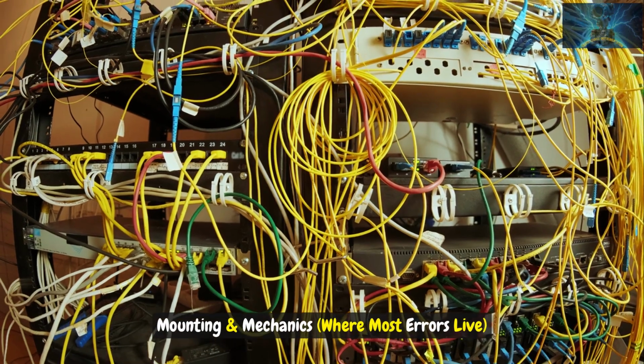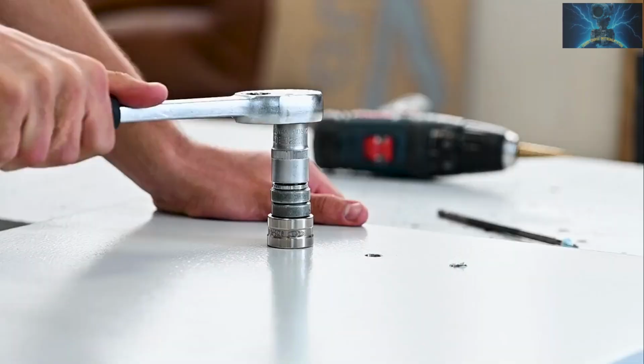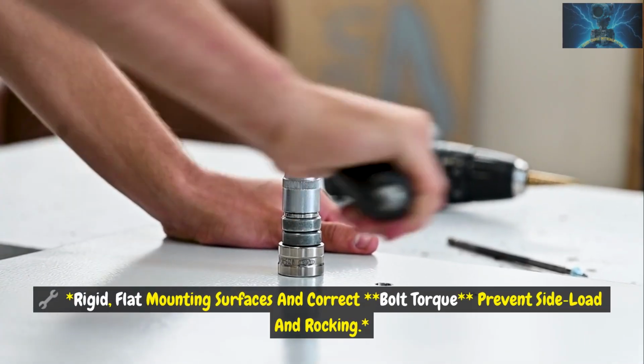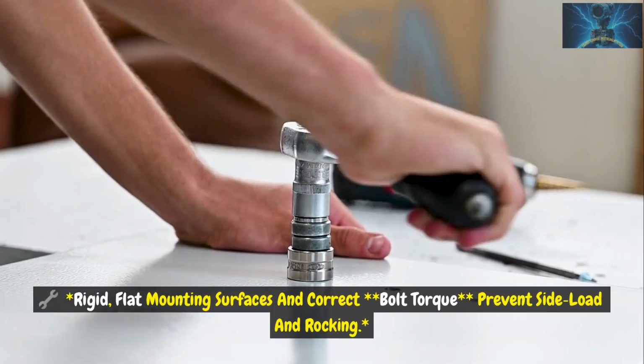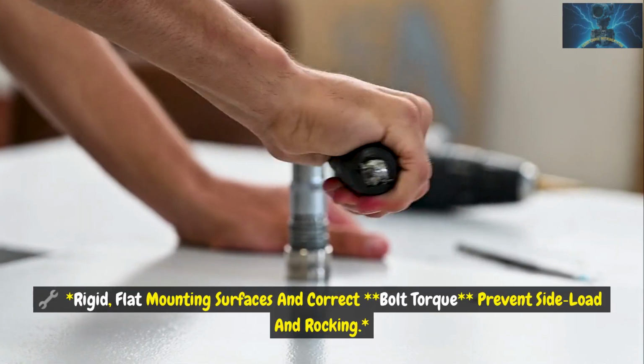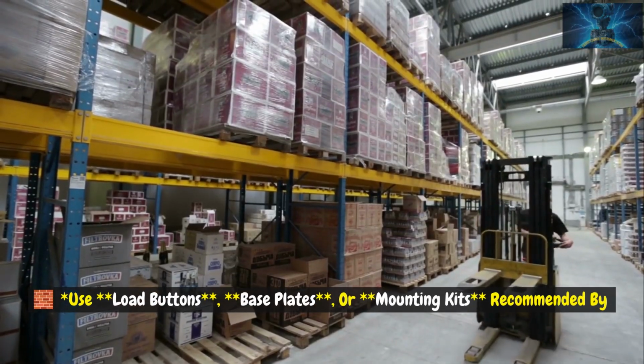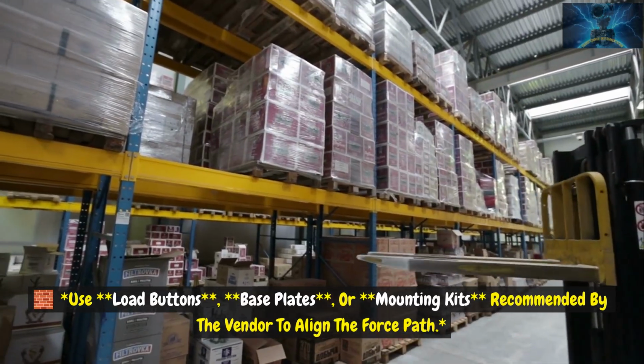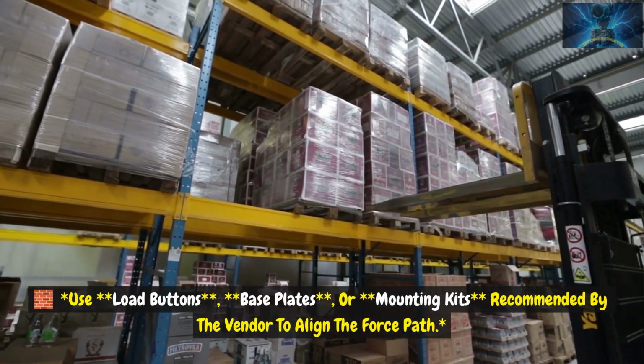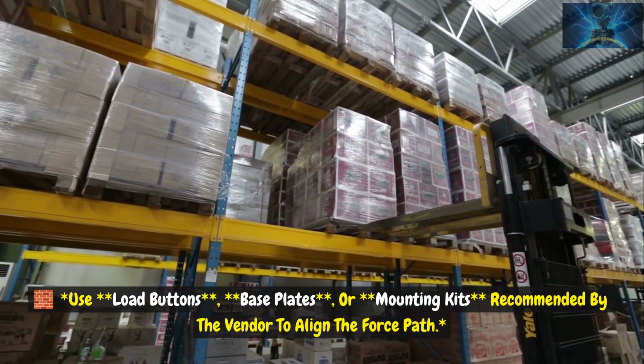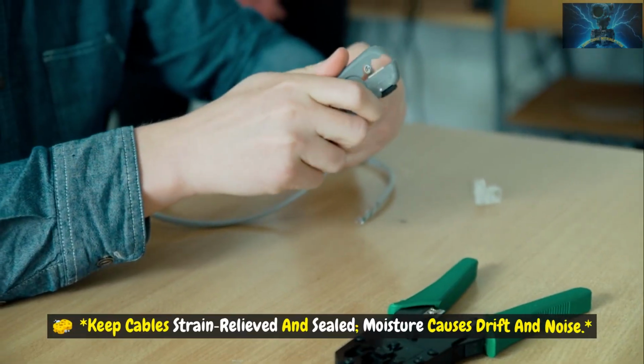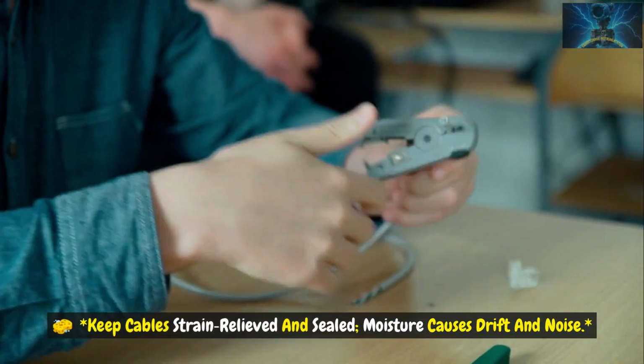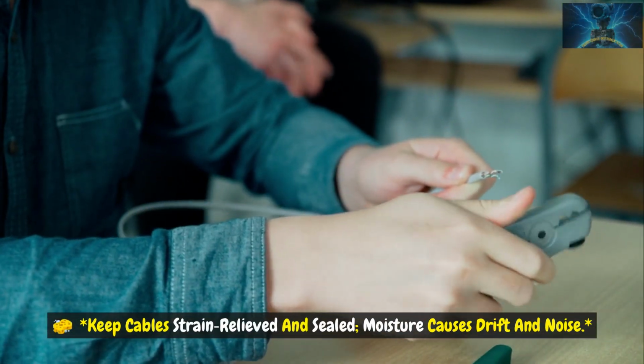Mounting and mechanics, where most errors live. Use rigid, flat mounting surfaces and correct bolt torque. Prevent side load and rocking. Use load buttons, base plates, or mounting kits recommended by the vendor to align the force path. Keep cables strain relieved and sealed. Moisture causes drift and noise.